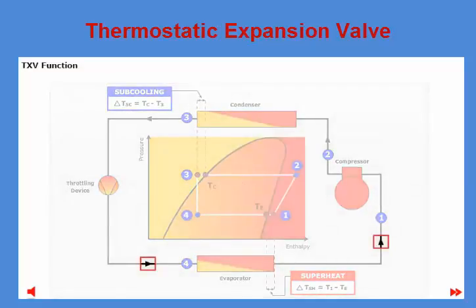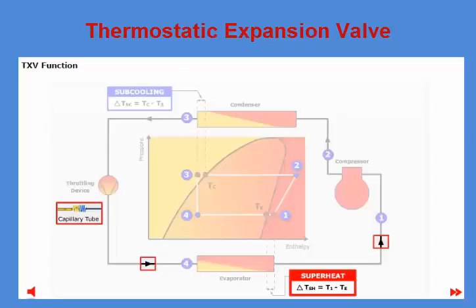The throttling device — from now on called thermostatic expansion valve — controls the superheat at the evaporator outlet. Because the compressor can be damaged if liquid enters it through the suction connector, it's important to always maintain a certain minimum level of superheat in front of the compressor. The simplest way of doing this is to use a fixed throttling device, such as a capillary tube, typically used in household refrigerators and other simple systems where optimization is not a selling point. A fixed throttling device can, however, only be effective for one set of operating conditions.